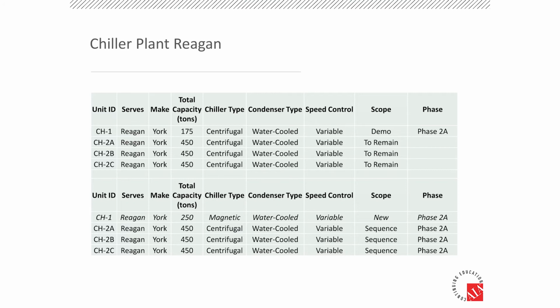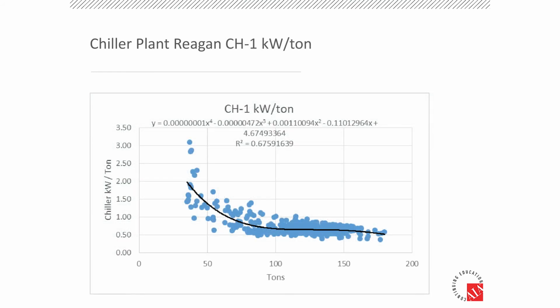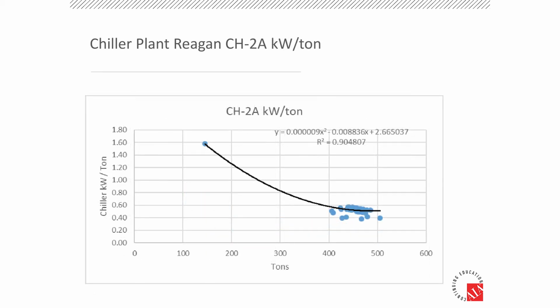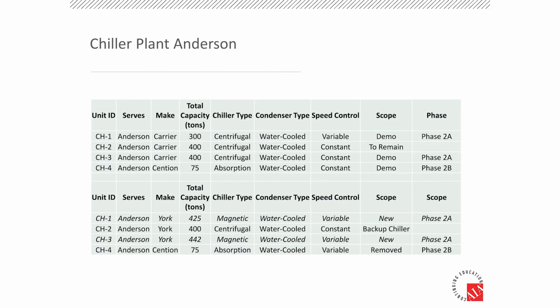This is how the plant operated before. You had that, we'll go back. We have this 175-ton chiller trying to do all of this load. And it just goes asymmetrical when it hits 50 tons. Has a hard time stopping from surging, has a hard time meeting building load. You have all the rest of the plant trying to compensate for it. This is what chiller 2A is doing. Unfortunately, when chiller 1 shuts down, this machine has to pick up this point, and then it takes off. So the perfect solution for us was to find a 250-ton chiller that could do that job.